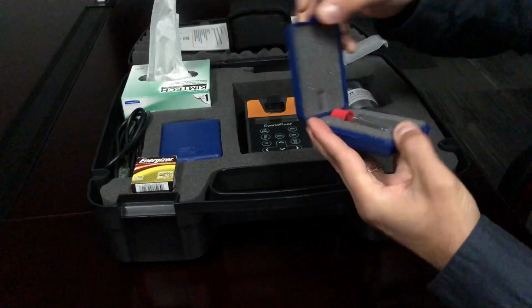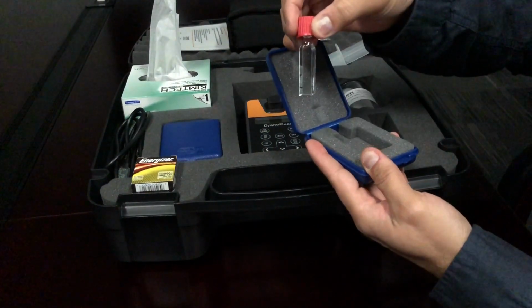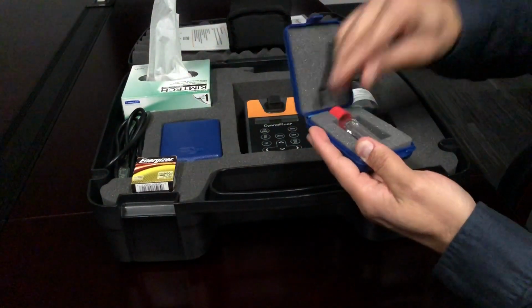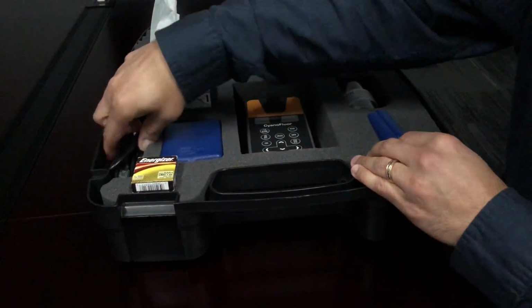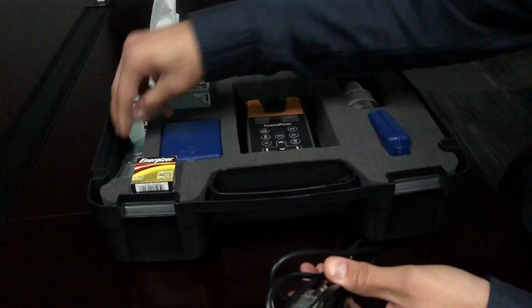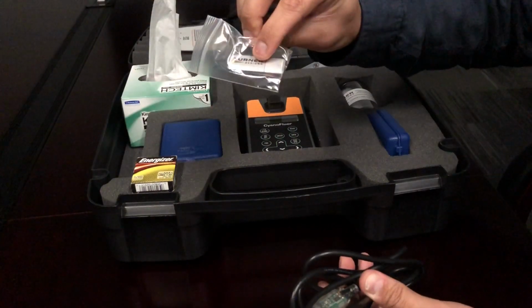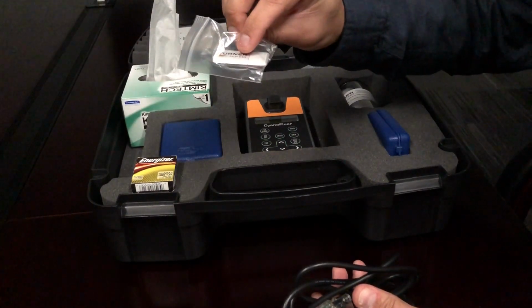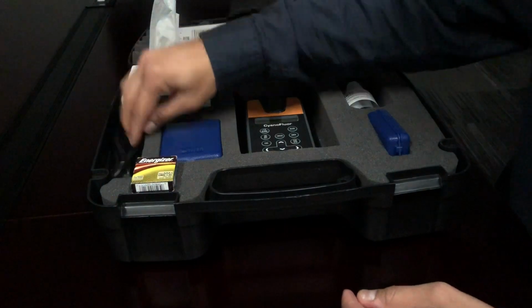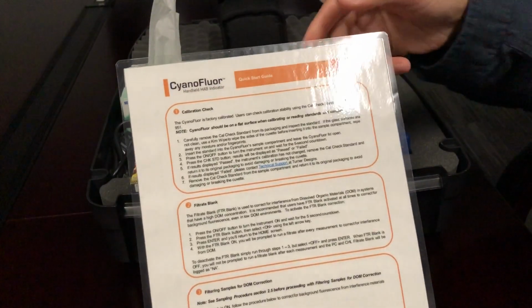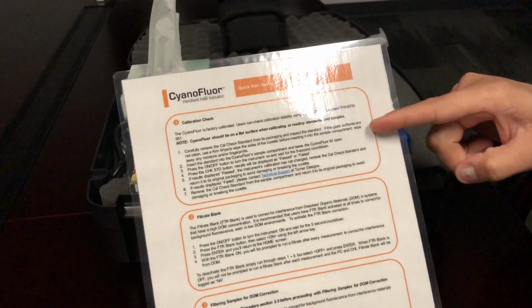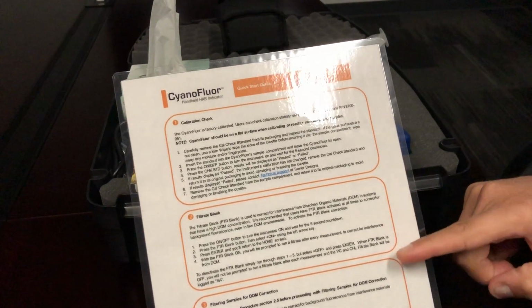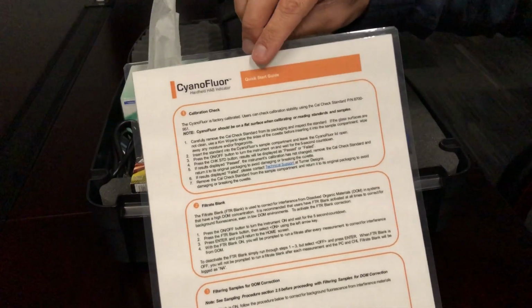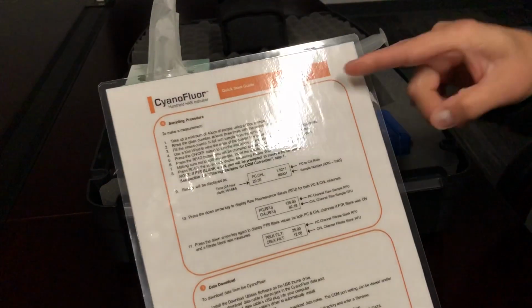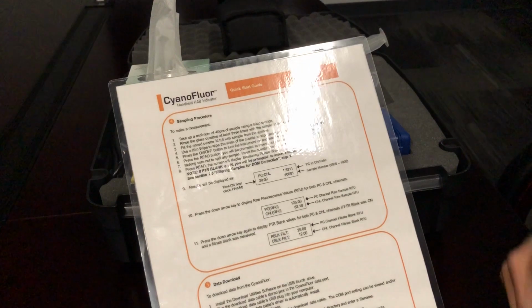Calibration check standard used for verifying the instrument's calibration. A USB data download cable along with a USB thumb drive, which includes the download utility software, and a quick start guide, which includes information on how to perform a calibration check, run a filtrate blank or filter for correcting for DOM, sampling procedure, and how to download data.